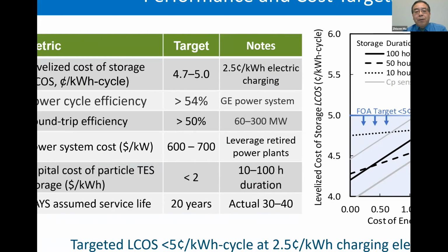But of course, those newly built gas turbine combined cycle plants are at a fairly larger scale, and it will be challenging for 300 megawatts to reach that price. But if we leverage retired power plants with their infrastructure and some components, we still can achieve that power system cost. And with a particle storage cost of less than $2 per kilowatt hour, we're fairly confident that we can achieve our target, even for the most challenging case of 100-hour long duration storage.